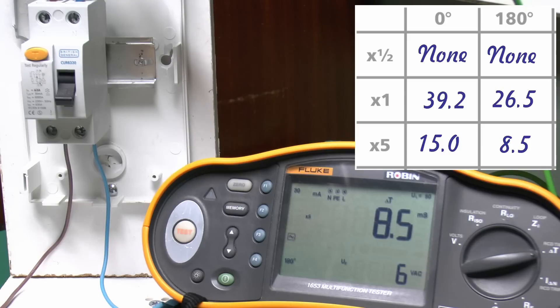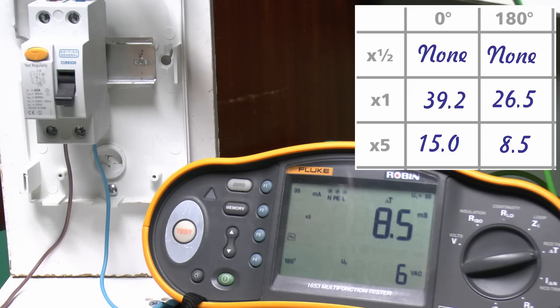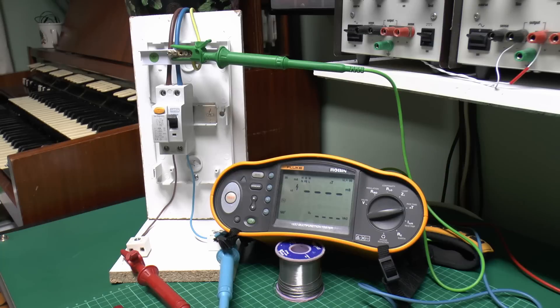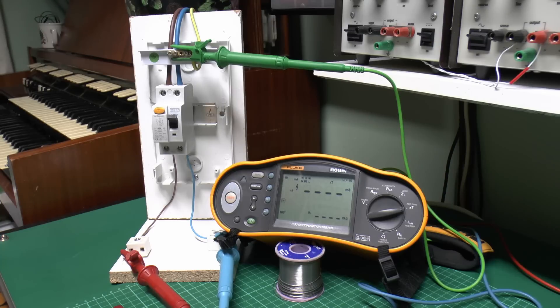And for the times 5 setting, the maximum tripping time is 40 milliseconds. So again, 15 and 8.5 are both well within that. Now those are all the tests completed for that particular device, and all of those were a pass.